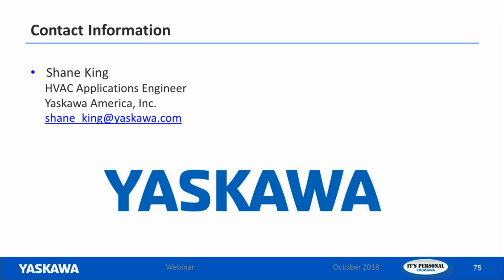And we can run a harmonic analysis. Building automation runs harmonic analysis to see if you actually need multi-pulse or Z1000 matrix drives. Yes, as long as you have the information we need on the system, such as the transformer that the drives are going to be on, we can make sure that you're not having to buy more harmonic mitigation than you need. We'll get you just what you need.